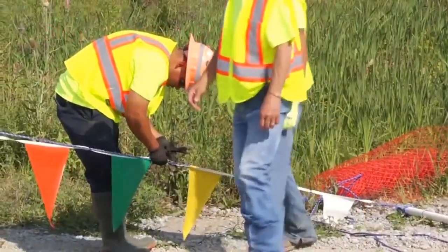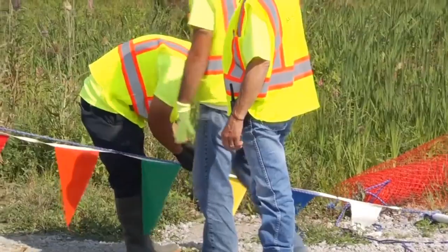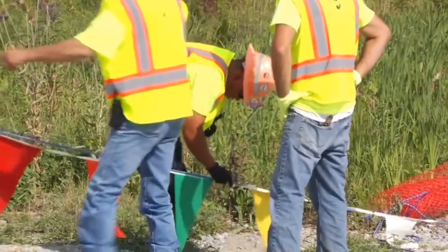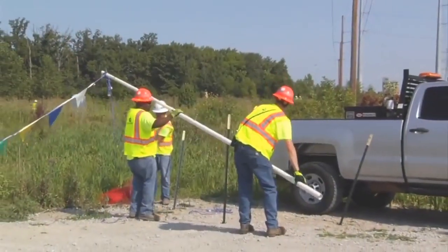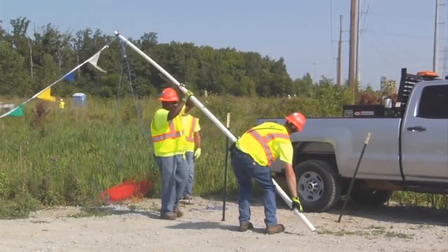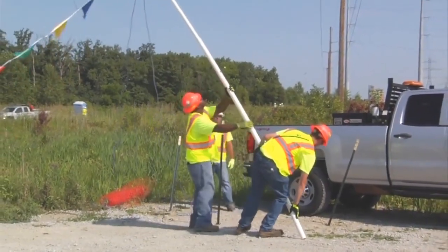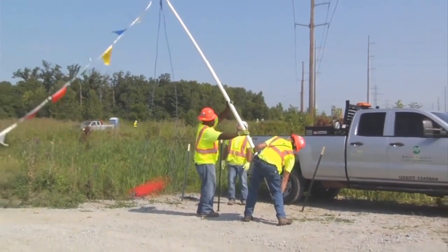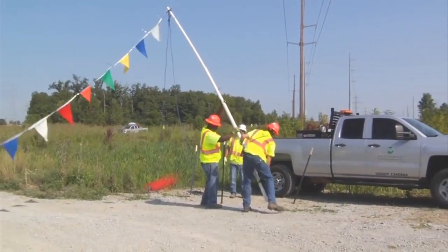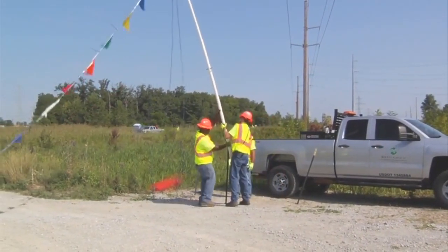The contractor shall also erect and maintain an elevated warning line, barricades, or line of signs, which shall be in view of the equipment operators. These lines, barricades, or signs shall be equipped with flags or similar high visibility markings at the minimum approach distance.